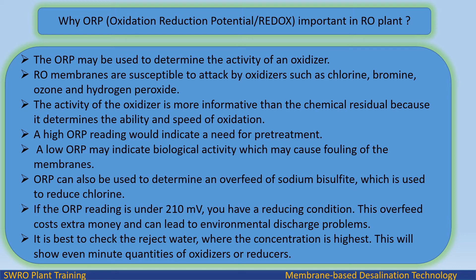A low ORP may indicate biological activity which may cause fouling of the membranes. ORP can also be used to determine an overfeed of sodium bisulfite, which is used to reduce chlorine. If the ORP reading is under 210 mV, you have a reducing condition. This overfeed costs extra money and can lead to environmental discharge problems. It is best to check the reject water where the concentration is highest, as this will show even minute quantities of oxidizers or reducers.